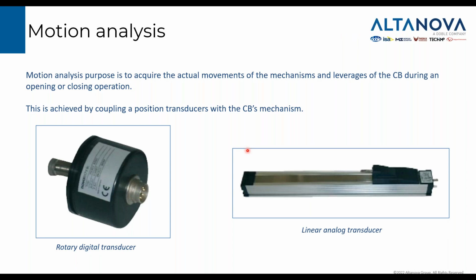There is the possibility to introduce in your measurement setup travel transducers or motion transducers. The purpose is to acquire the actual movement of the mechanism during the open and close operations. There are, let's say, two main families of transducers, rotary and linear. The choice between the two depends very much on the mechanical layout and design of the circuit breaker you need to test.